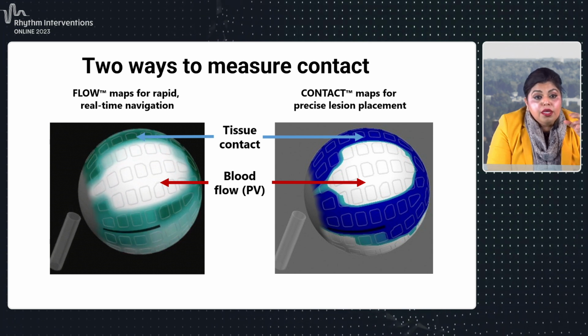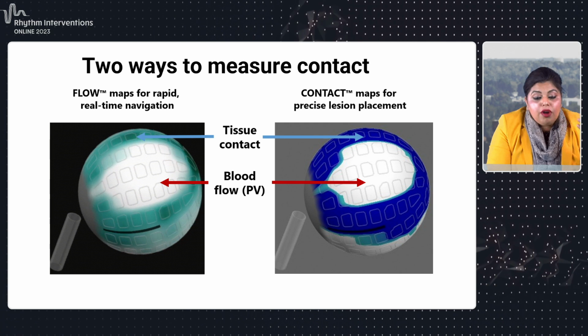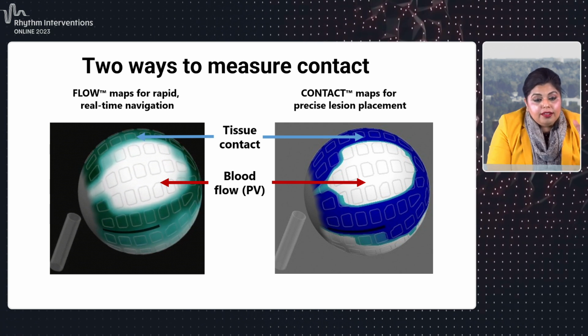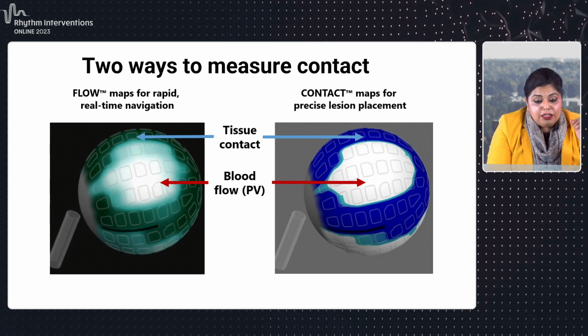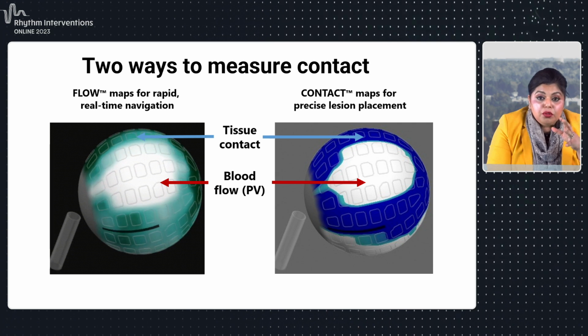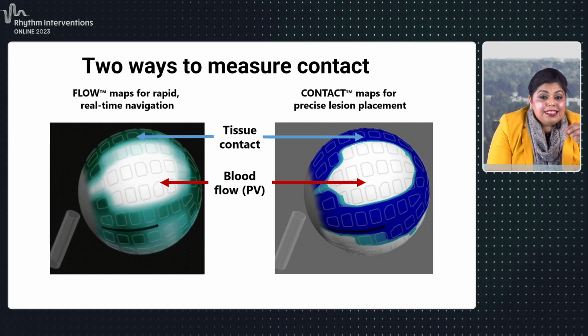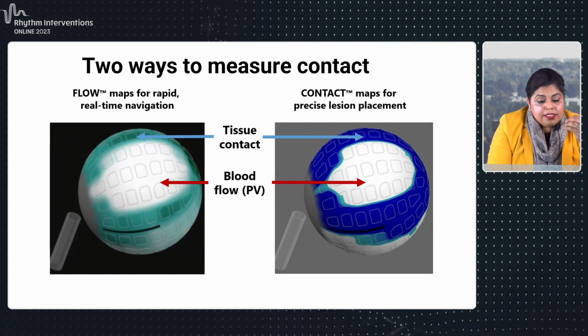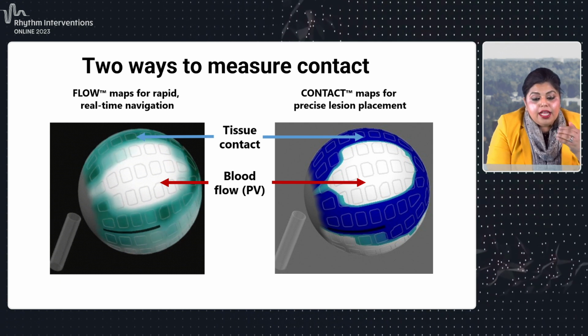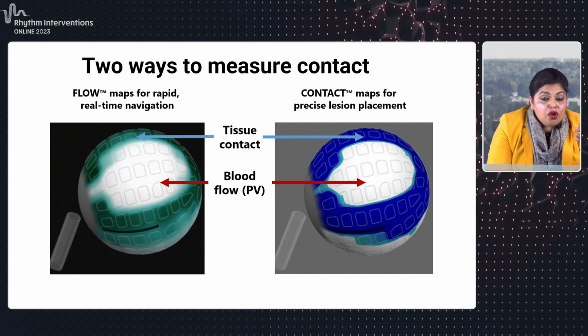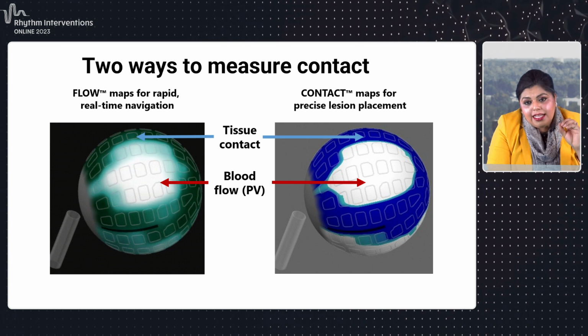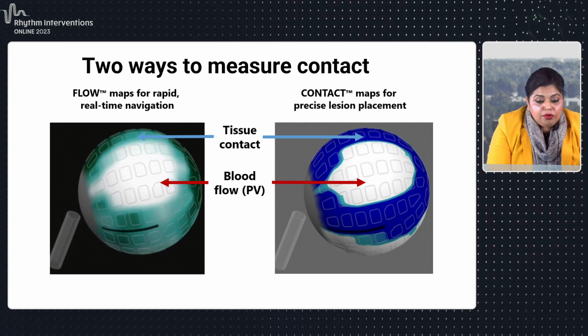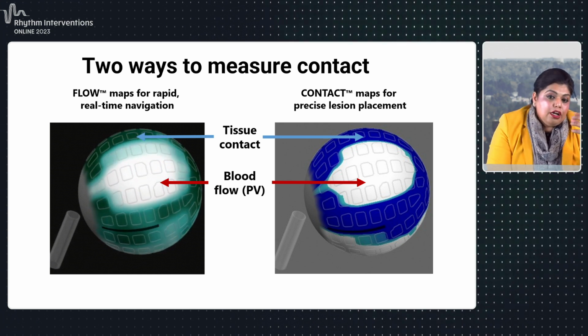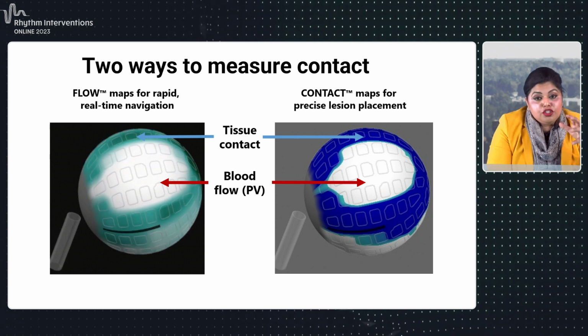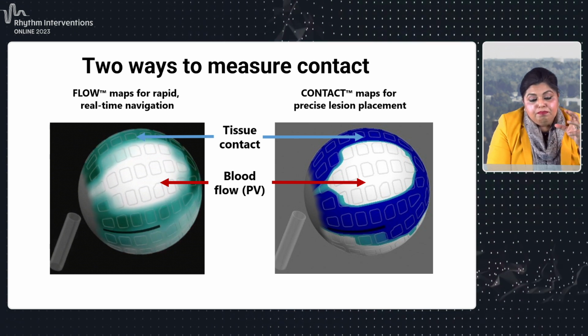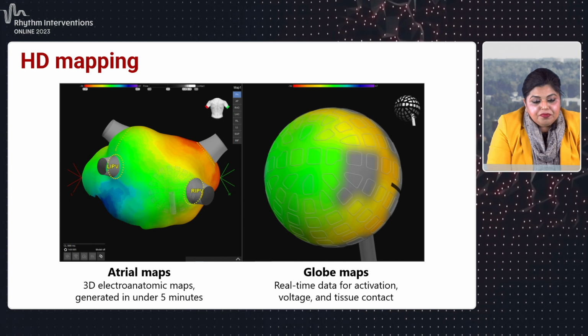And it's a way to do real-time navigation and rapid mapping as you're moving the Globe array around the left atrium. Now, the contact map, which is on the right side, measures differences in the rate of heating. So it delivers a subthreshold stimulus and measures that rate of heating and assesses contact in that way. And so that takes a few seconds, but it is more accurate, and that's what allows us to use a more precise lesion placement before we do the pulse ablation.